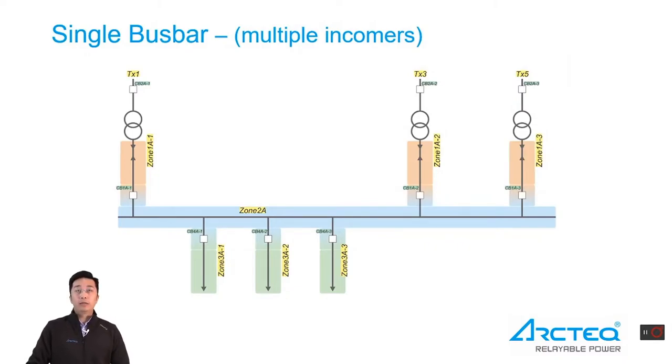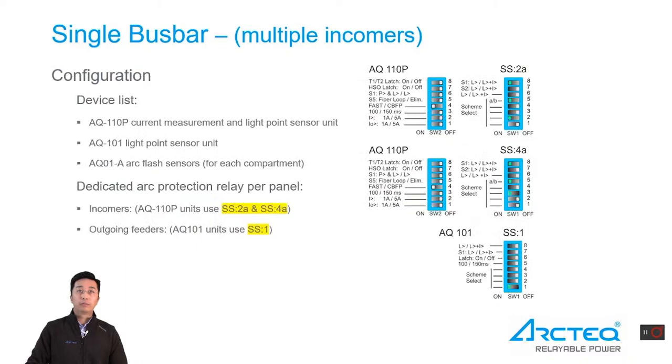The third application is a single bus bar with multiple incomers. There are multiple incomers and multiple outgoing feeders. For this configuration, we also use a full selective protection scheme. AQ110P units are for incomers, AQ101 for outgoing feeders, and AQ01-A arc flash sensors for arc fault detection. Standard schemes 2A and 4A are configured to AQ110P, and standard scheme 1 of AQ101 is used for outgoing feeder units.